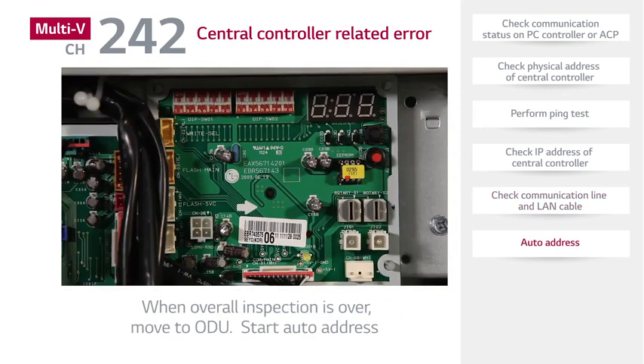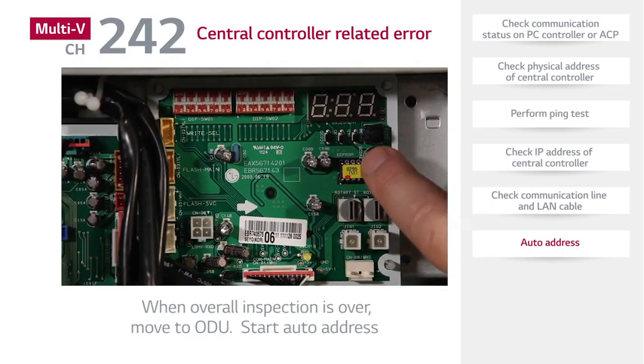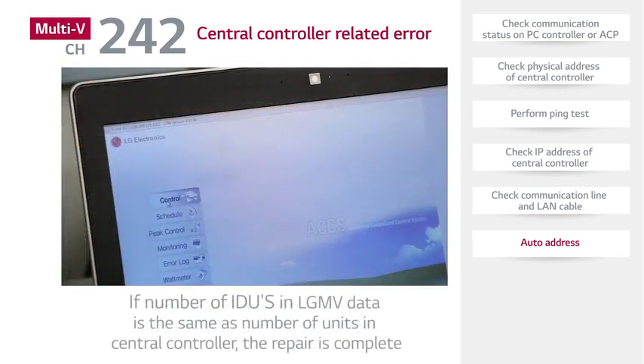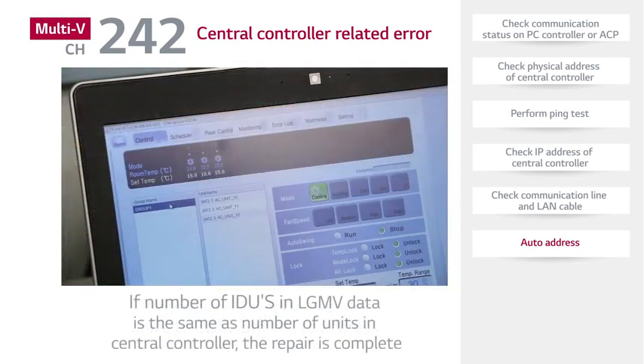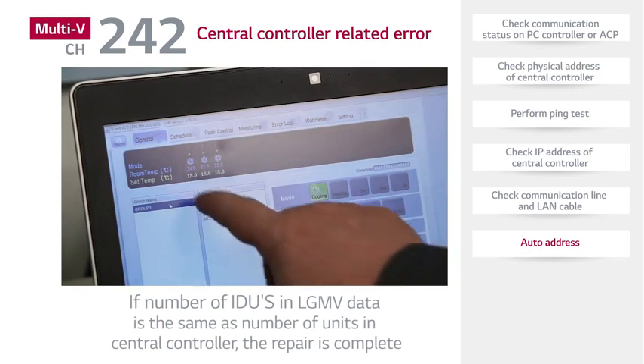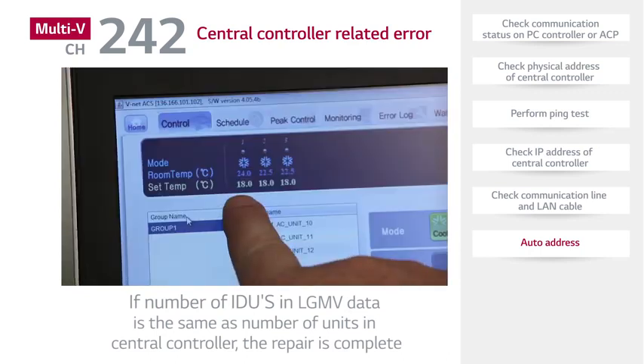Finally, perform auto address. If the number of indoor units in LGMV data is the same as the number of units in the central controller, the repair is completed.